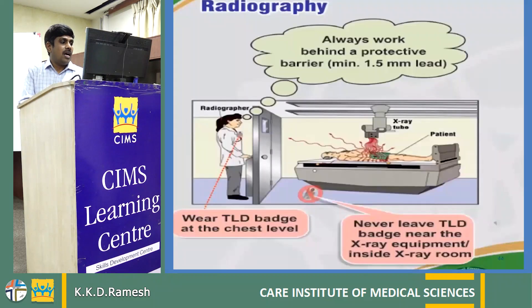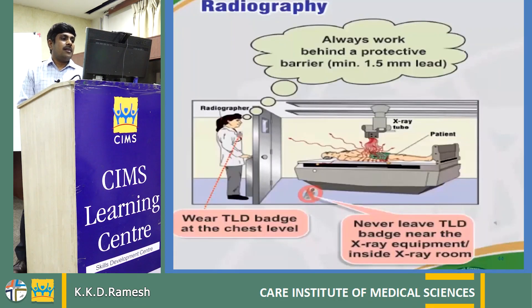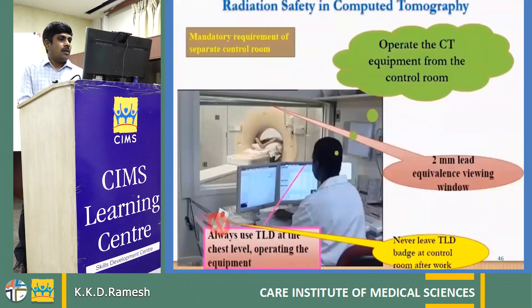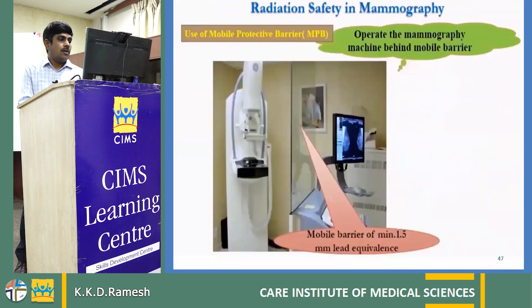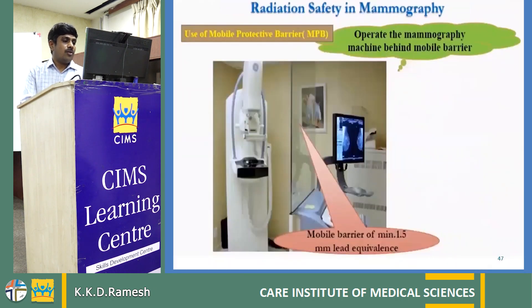For radiation protection in radiography procedures, always work behind the protective barrier. Always use an extendable control cable when using mobile X-rays. Always operate the CT from the control console, and always operate the mammography unit from the mobile lead barrier.